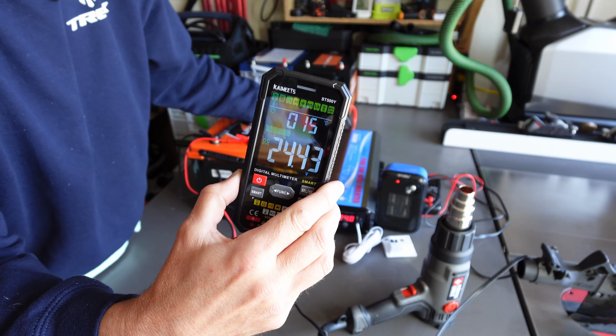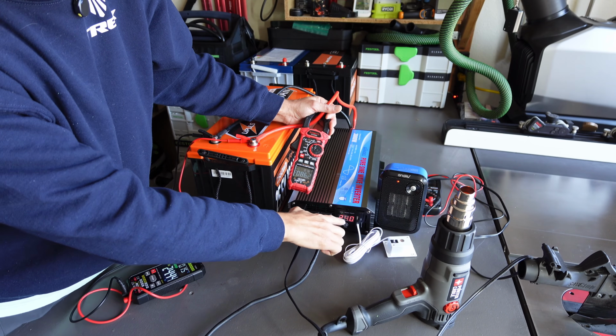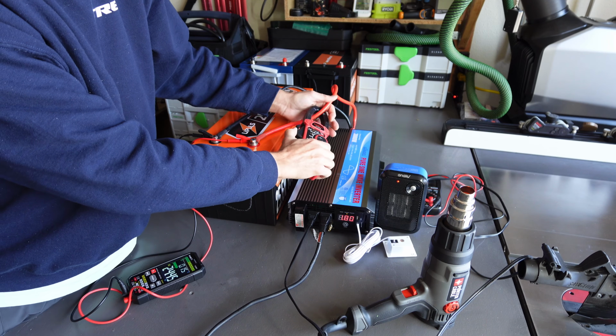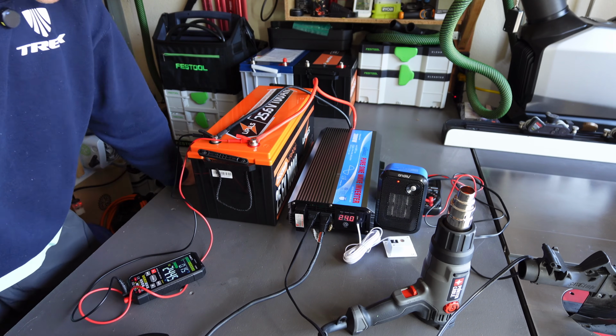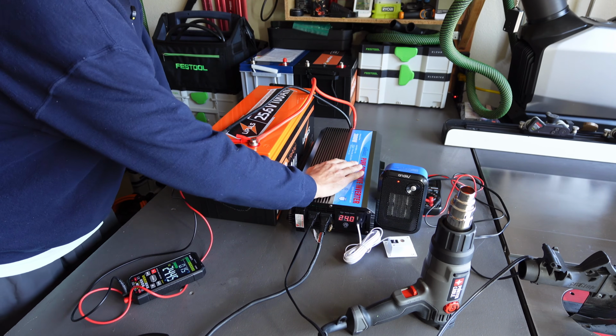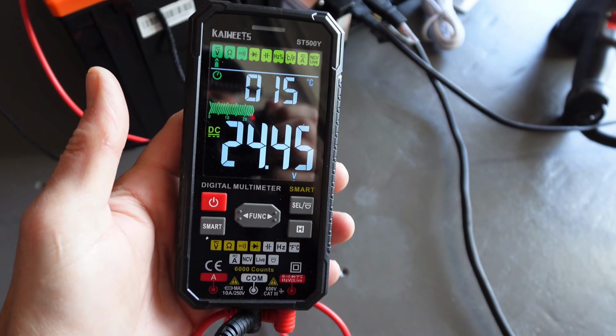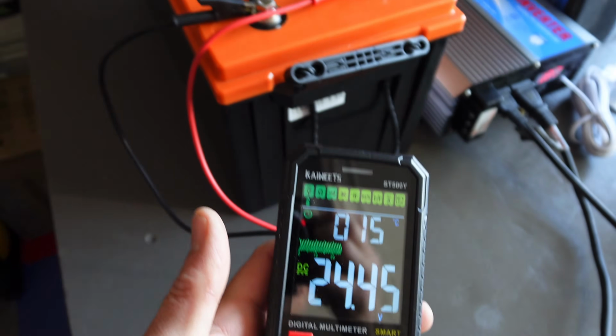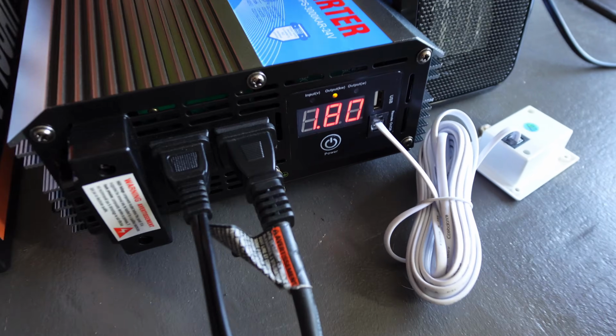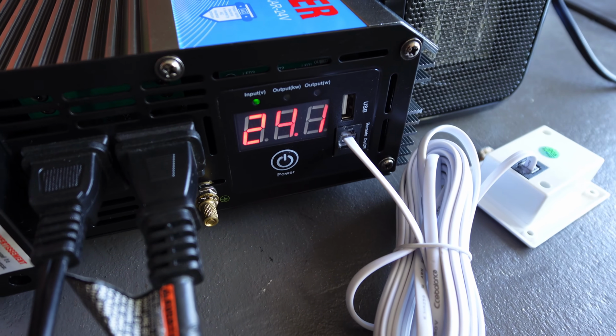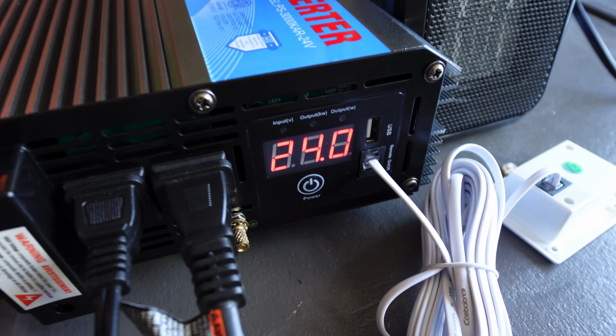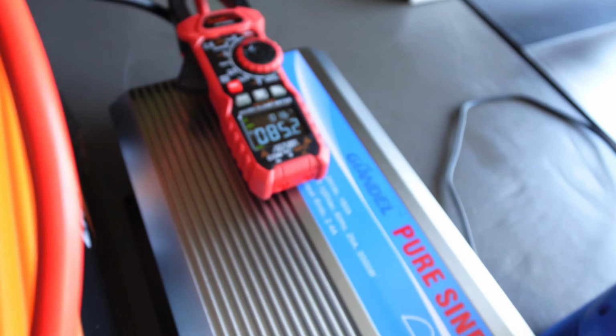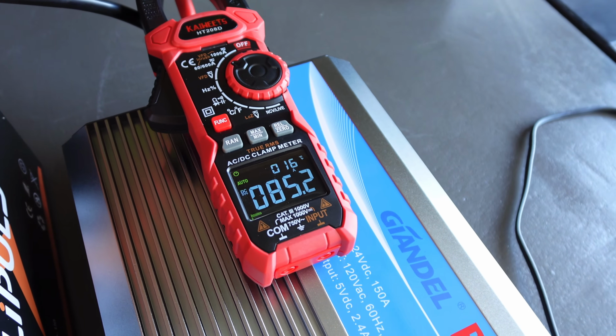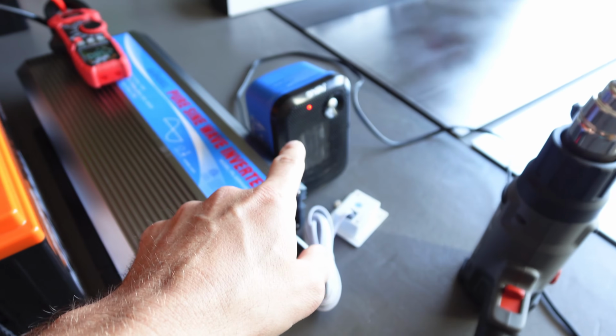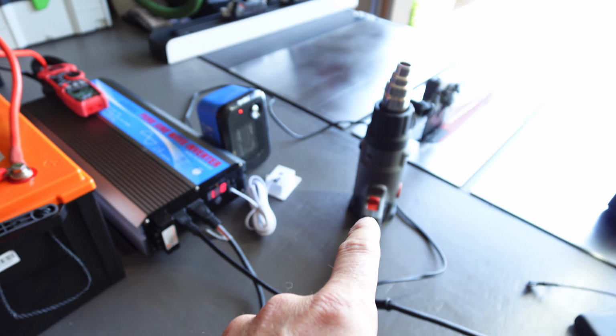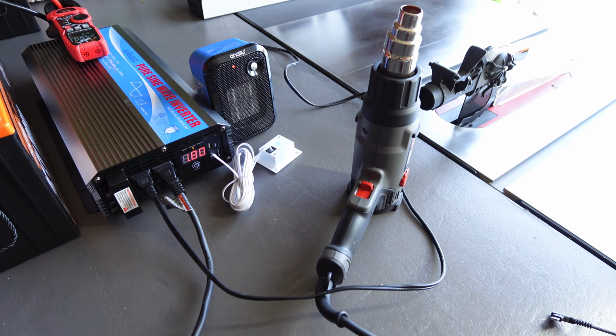24.43 volts directly from the battery, 24 volts showing on the inverter screen. Okay, up close, 24.45 connected directly to my battery, 24.1 off of the inverter. We are pulling 85 amps, running a 500 watt space heater and a 1500 watt heat gun.